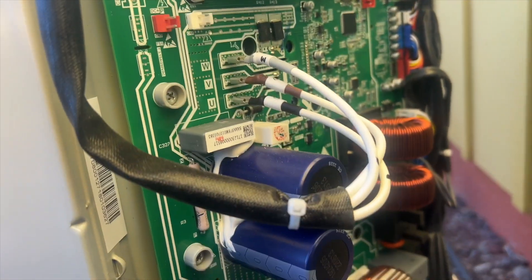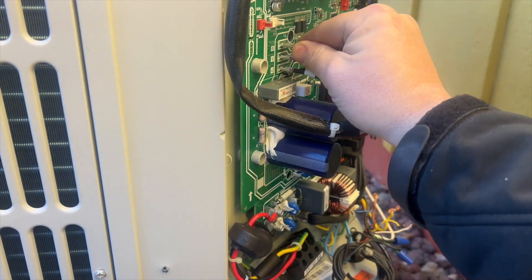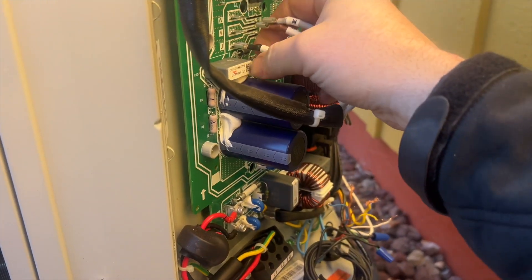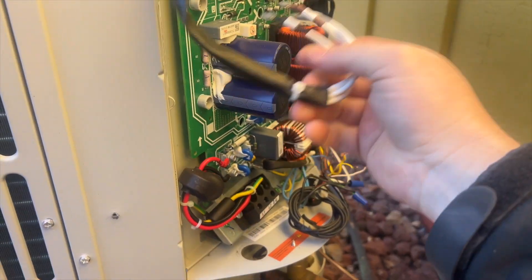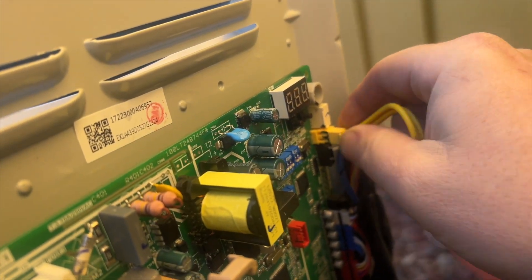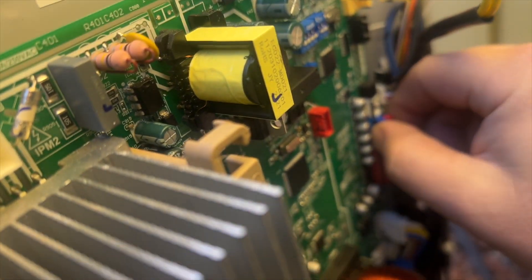I've made note of where everything goes, including which connectors have nothing plugged in, so I'm not wondering what goes where. We'll start with the compressor — pretty straightforward. This one's all labeled, which is nice: W, V, and U, right there on the board. I recommend taking pictures of everything, just to cover yourself. Yellow to yellow — they make these things pretty easy with color coding and design them so you can't plug in the wrong thing, which is a nice touch.